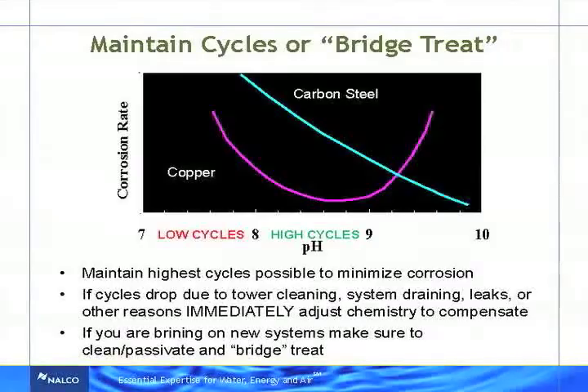Unplanned would be, the pressure valve pops and you lose some water out of there, or maybe you've got a leak in your condenser system, or overflow on your tower because the level control gets stuck up and it just starts overflowing. That would be unplanned. During those periods of time, don't just say, hey, I'm losing water, let's fix it. Also check to see what impact that has on your overall chemistry, because it can change a lot of the ranges that you should be running. So keep an eye on those things.